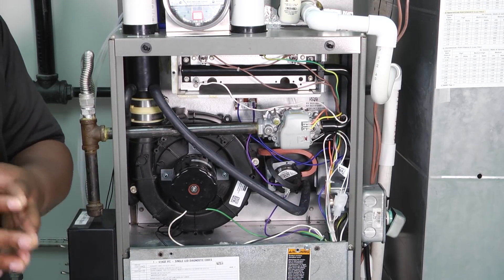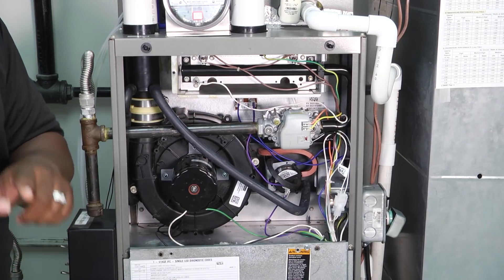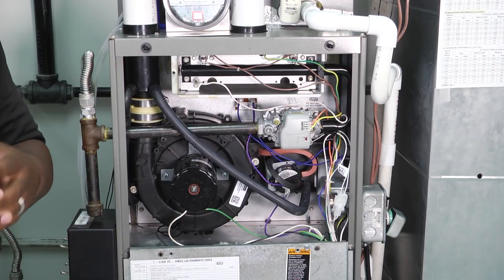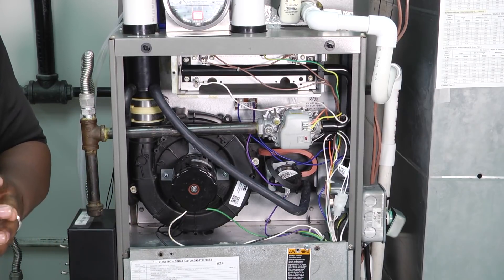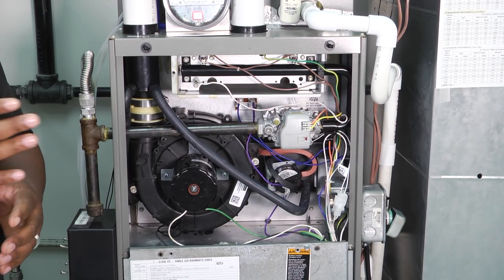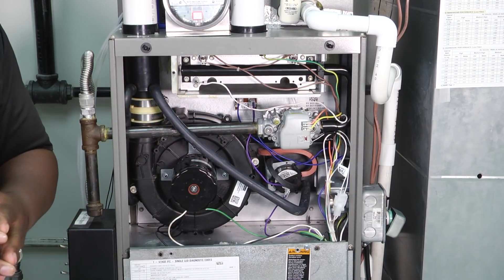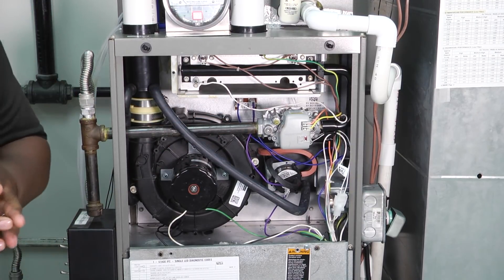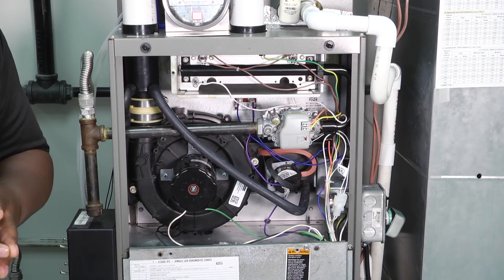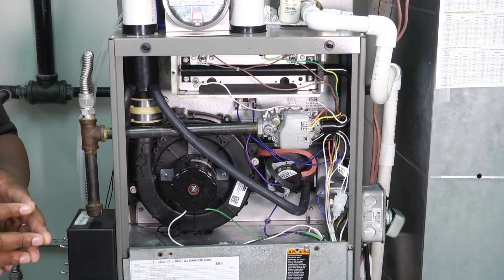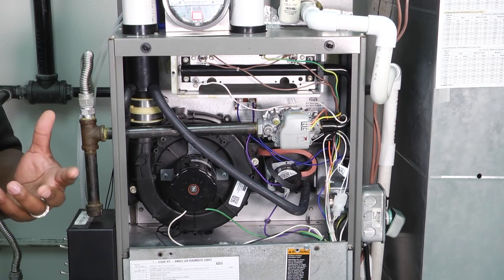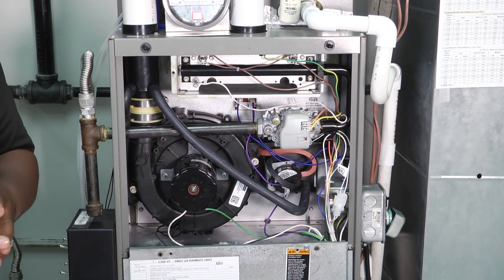When we speak of total static pressure, we're talking about force being exerted in all directions within our ductwork, versus velocity pressure which only exerts force in one direction. Our ability to take readings and measurements of total static pressure gives us insight into what's going on with airflow or airflow issues within our system.